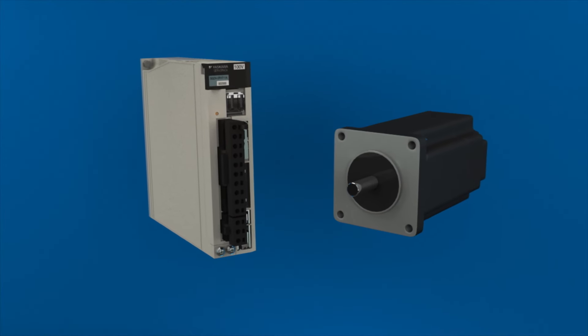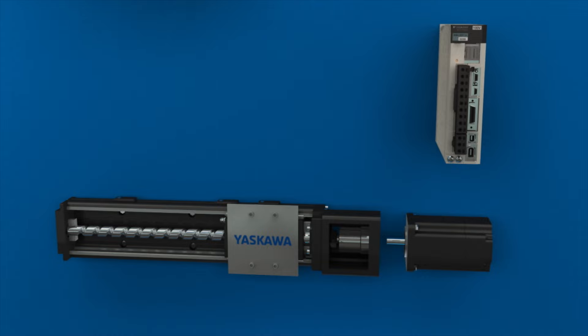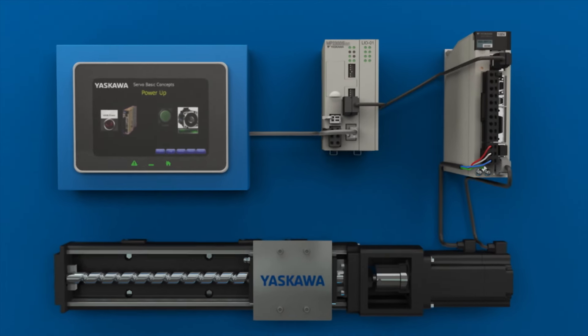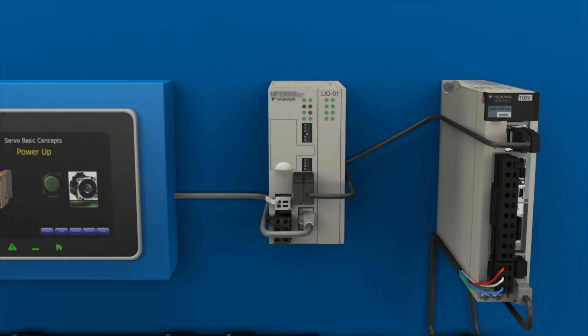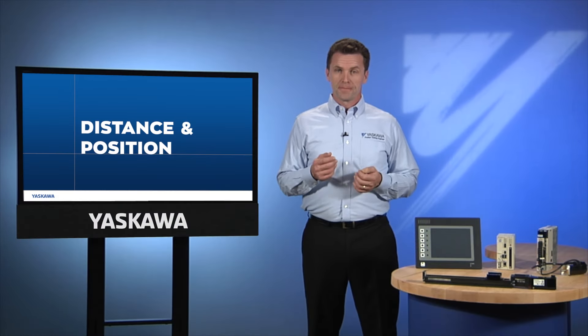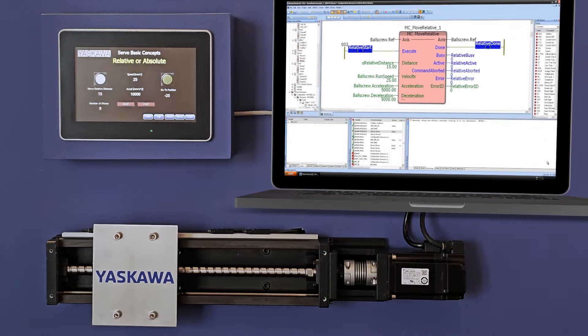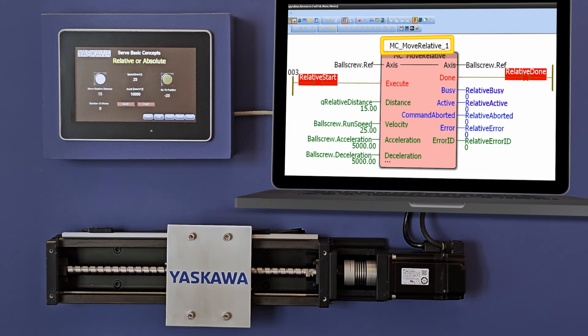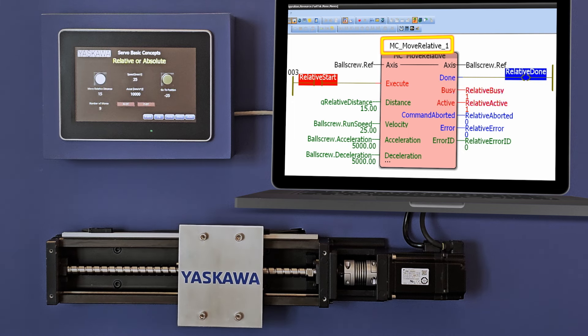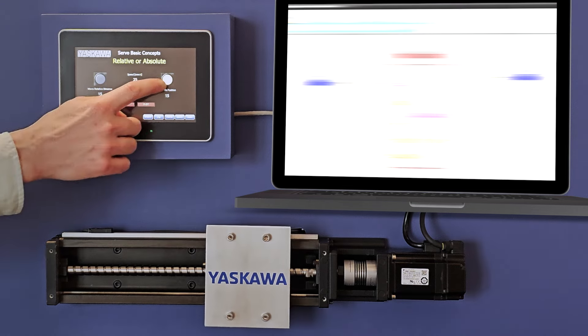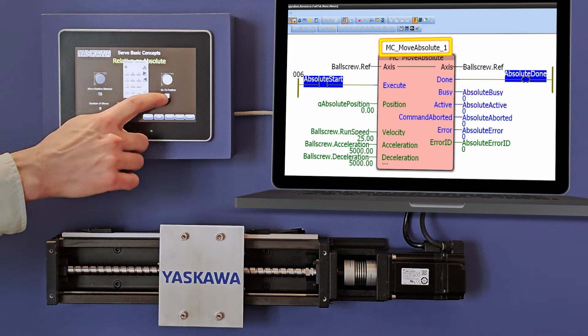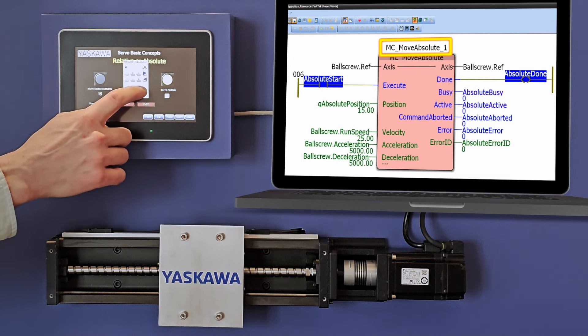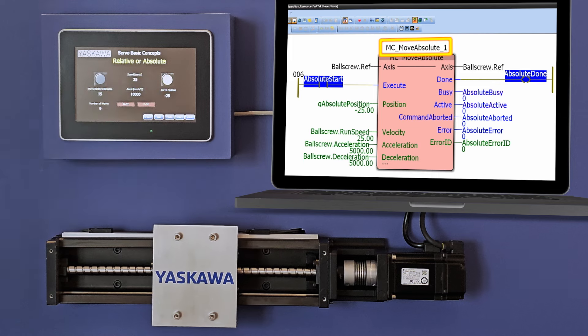While the servo amplifier and servo motor are the devices at the heart of the motion control system, let's move our discussion upstream to the controller, where all the commands originate. The topic of controller programming is beyond the basics, but we can cover some fundamentals like distance and position. The program may require the servo mechanism to travel a certain distance relative to its current location — this is called a relative move, and this approach is helpful when programming a move that needs to repeat itself several times. On the other hand, the program may have a preset table of positions to which the machine is to move, and an absolute positioning move to a certain position can make programming the controller a lot easier.